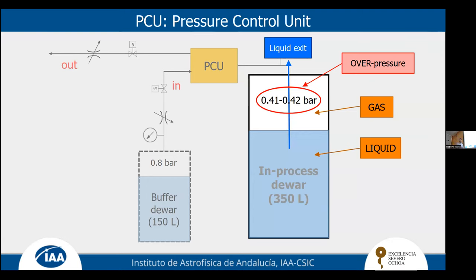Depending on this pressure, the amount of liquid nitrogen that goes to the system changes. This is basically how we can extract the liquid from the bottle with the overpressure. But there's some sources of instability that change this pressure, for example the exchange of bottle every day, or the lower of the level.